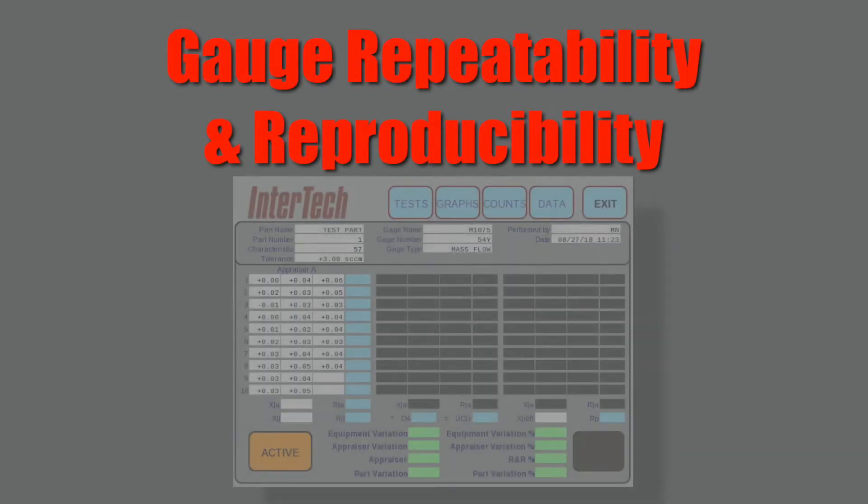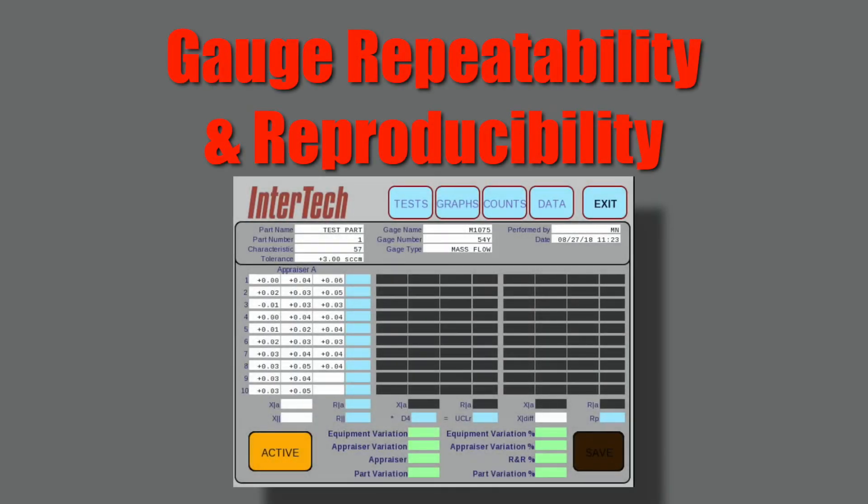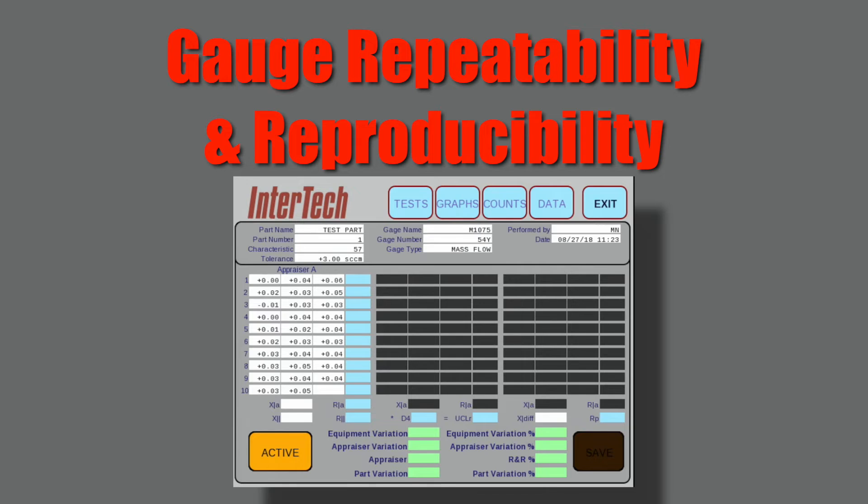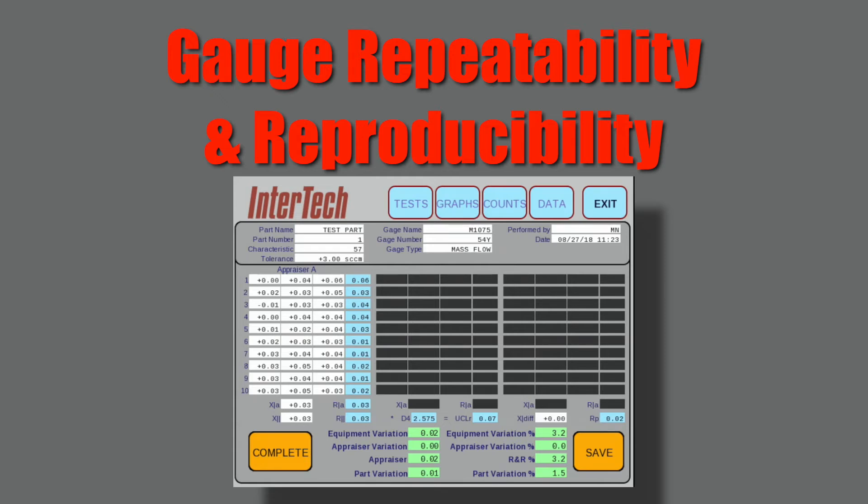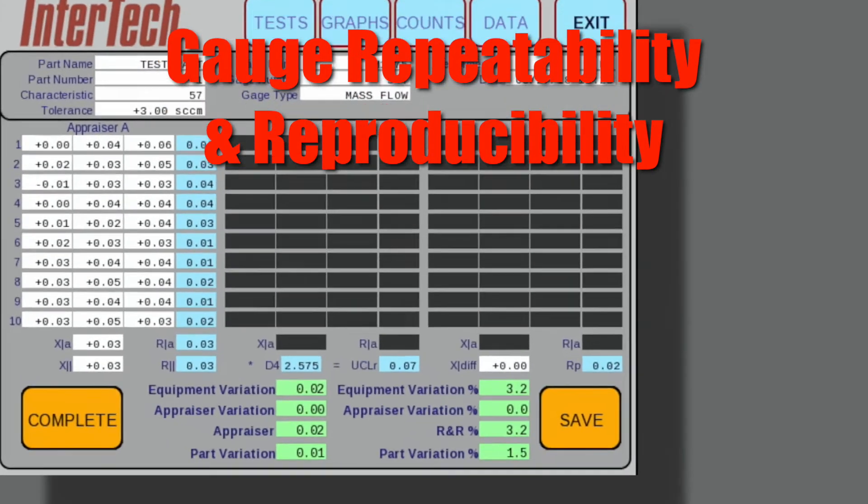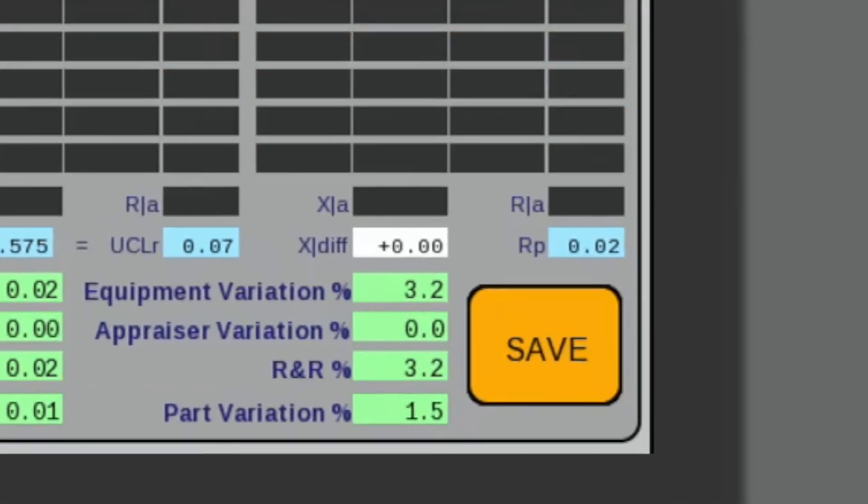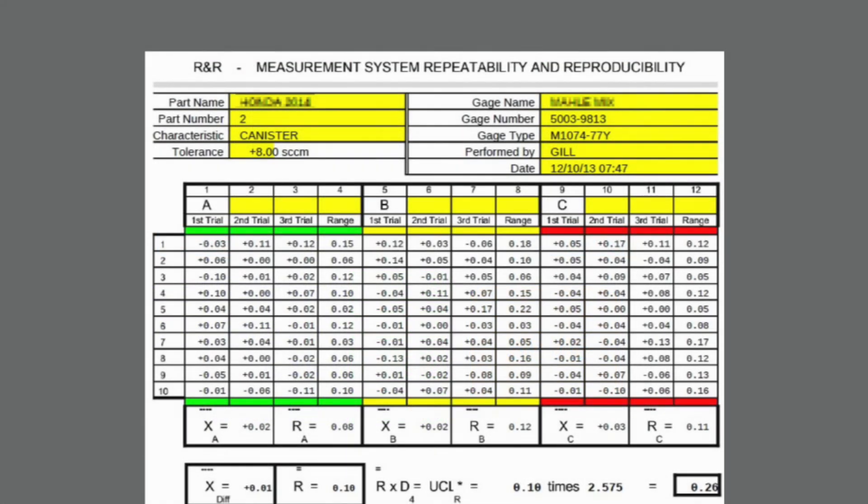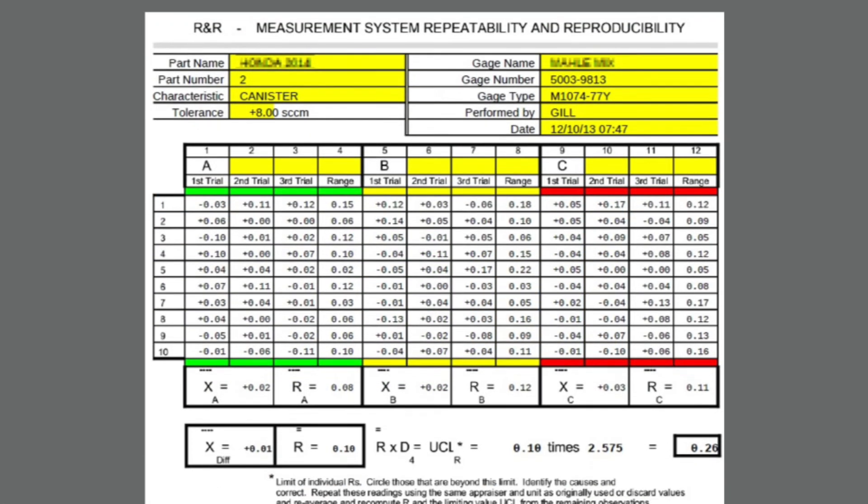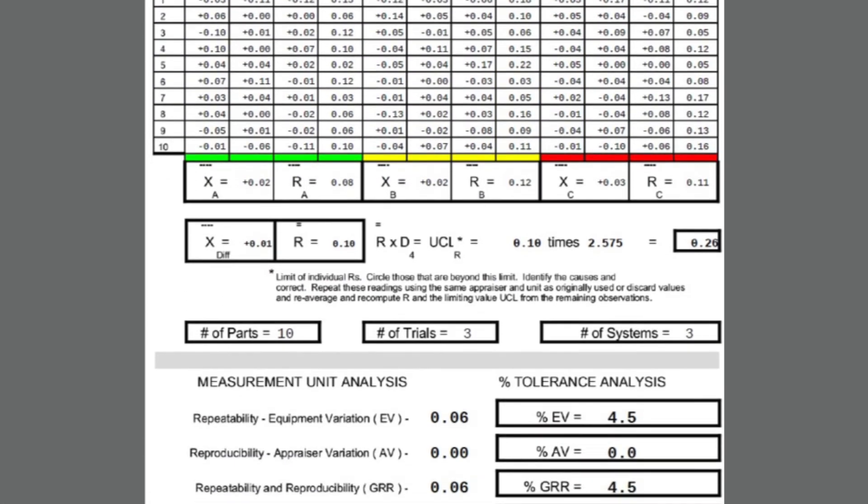The M1075 standard programming includes the gauge reproducibility and repeatability mode, which allows the user to determine the performance of their measurement system, taking into account the test instrument, the test fixture, the test part, and the operator's variations. Running 10 parts three times is a typical evaluation process. GR&R reports can be saved to a PDF file using the USB port by pressing the save button, which generates a printable report of the evaluation.